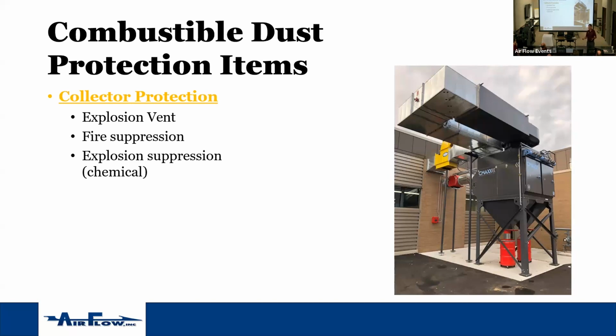And then another way to do it is to just put an explosion suppression chemical system on it. A lot of times you don't have wet sprinkler lines in buildings, or no one wants to deal with trying to put a wet sprinkler line to a collector that sits outside and all the safeties that are involved with protecting it from freezing. So we'll put chemical suppression on it.